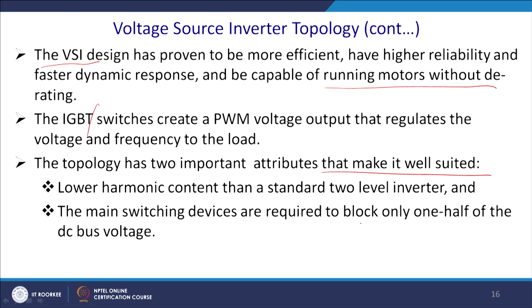IGBT or GTO, whatever it may be, if you wish to have a little higher frequency, go for the IGBT. Nowadays, with the penetration of high bandwidth devices like SiC, we can have IGBT switches create a PWM voltage output that regulates the voltage and the frequency to the load. The topology has 2 important attributes that make it well suited: lower harmonic content than a standard 2-level inverter, and the main switch devices are required to block only 1/2 of the DC bus voltage.